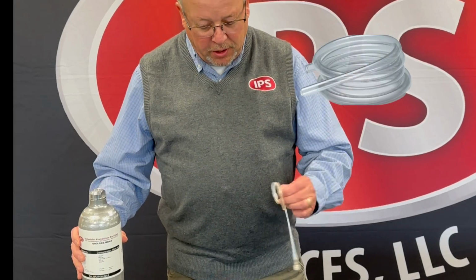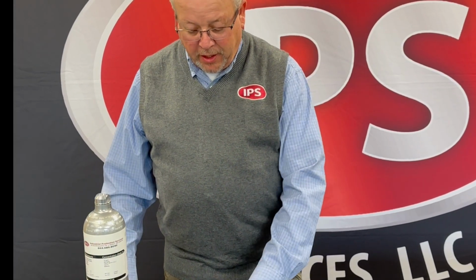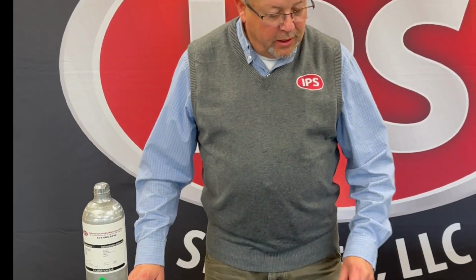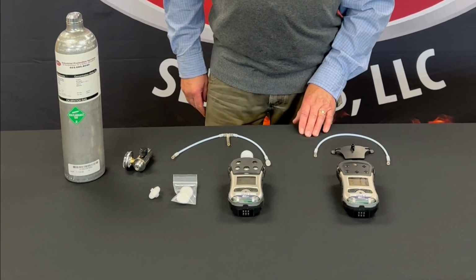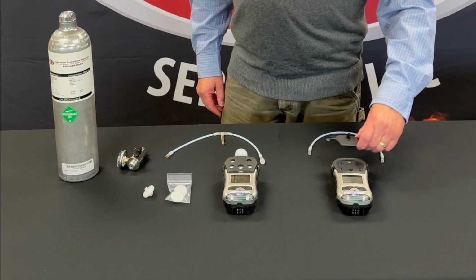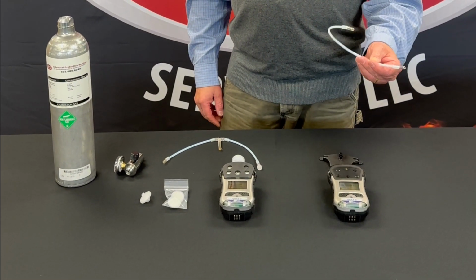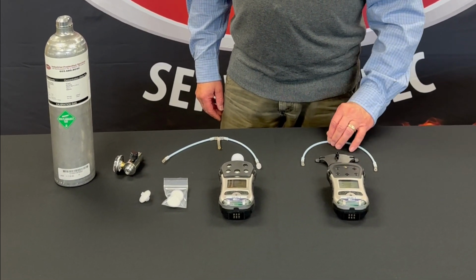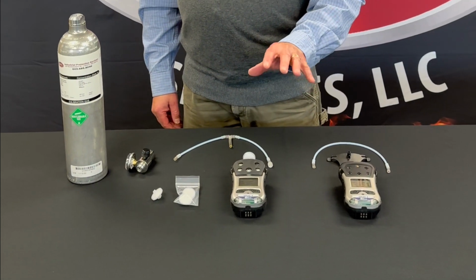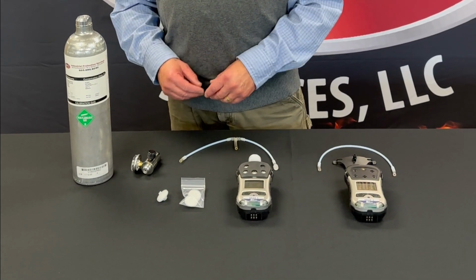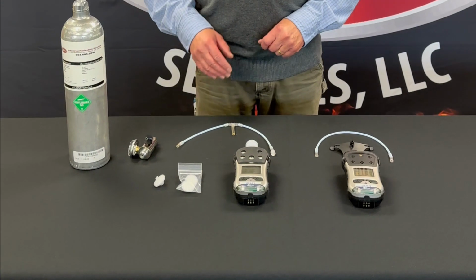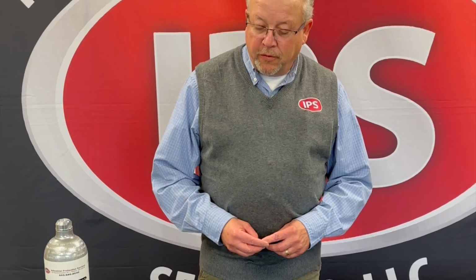I've got my adapter for the pump module. I've got a calibration regulator head. And for those of you that have a diffusion monitor, I have the adapter as well as the calibration tubing for that. The calibration procedure for either monitor is exactly the same. Today we'll do the calibration on the pump version.